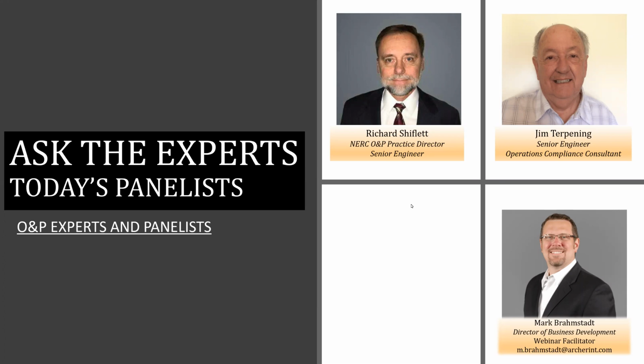I've seen entities approach this two different ways. Either A, they list the generator step-up transformer separate from the CTs in their facility ratings and give ratings for both, essentially based on the nameplate of the transformer. You can use IEEE standards to rate a transformer, but generally, in most situations I've seen, not all, they'll use the manufacturer's nameplate.